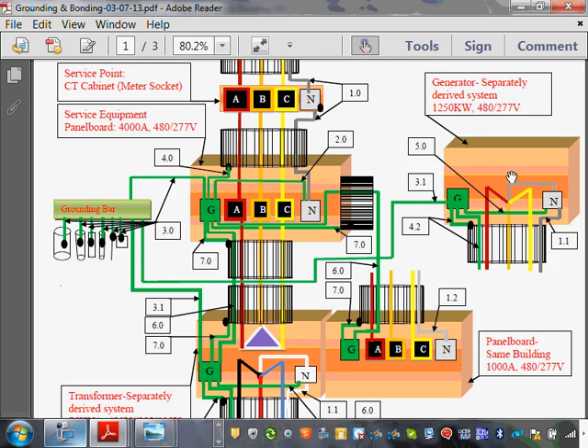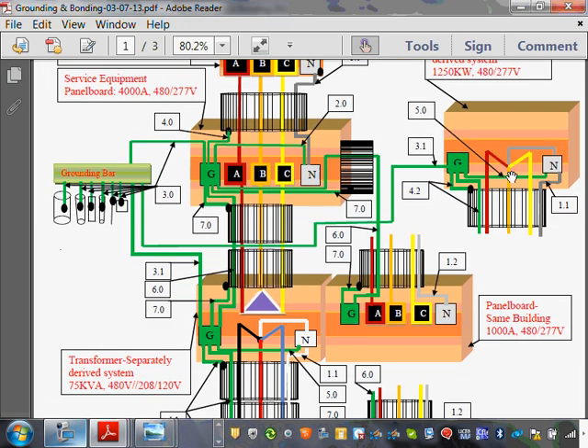Why do I size the neutral? Because the neutral, guys, is a grounded conductor. Our topic is what? Grounding and bonding. Neutral is called the grounded conductor. So that's why I'm worrying about the neutral. You need to know how to size it. Okay, so we size our neutral, guys.